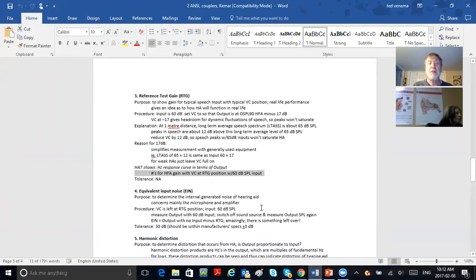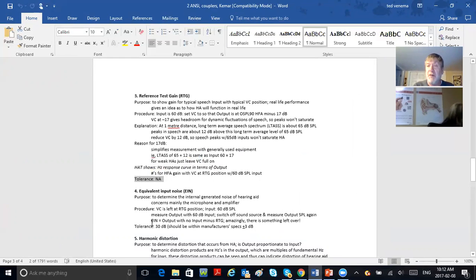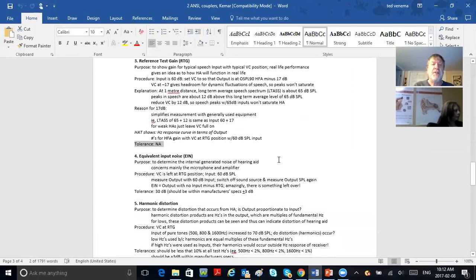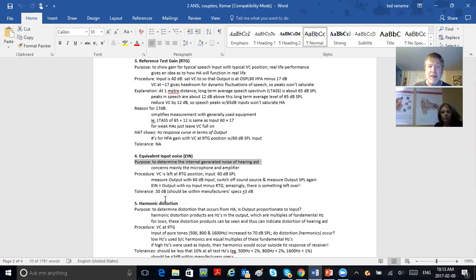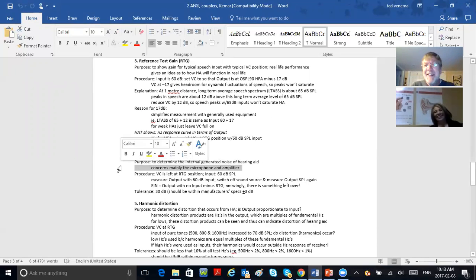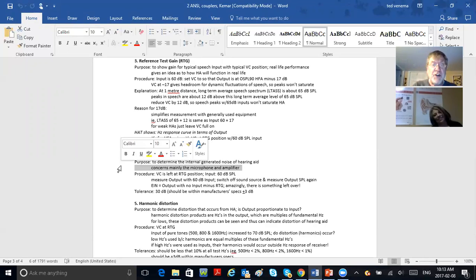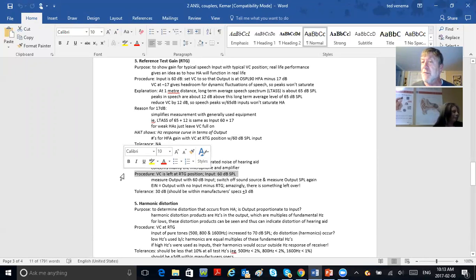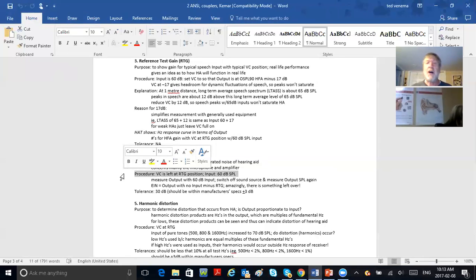Number four: equivalent input noise. The purpose is to determine the internal noise generated by the hearing aid—noise from the microphone and amplifier. It concerns the hardware. The procedure: leave the volume control at reference test gain position. By the way, you're not doing all of this manually—you put the hearing aid on the 2cc coupler, close the lid, push the button for ANSI testing, and OSPL 90 and full-on gain are done automatically.